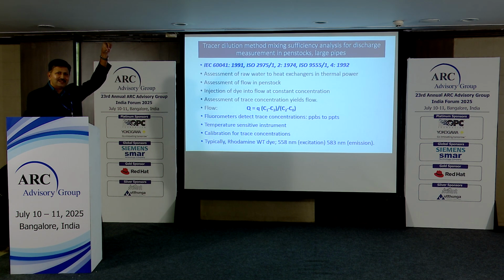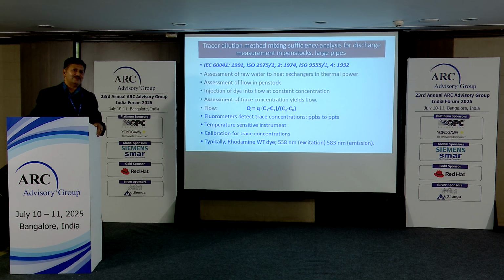You know that when something is introduced into a flow, depending on the flow velocity you have a high or low concentration, depending on whether the flow is low or high, right? Anything that is introduced, if it is stretched over a length due to high velocity, will have its concentration come down. What is required at the power station is that, when you introduce it, you need a sufficient straight length of pipe. It could be more than 200D, 100D, or 150D to have a sufficient length.